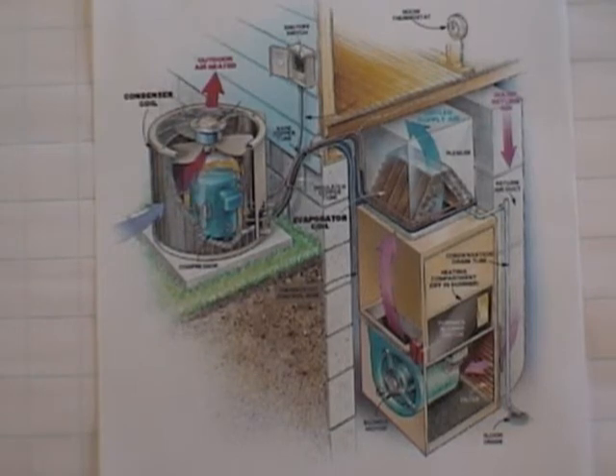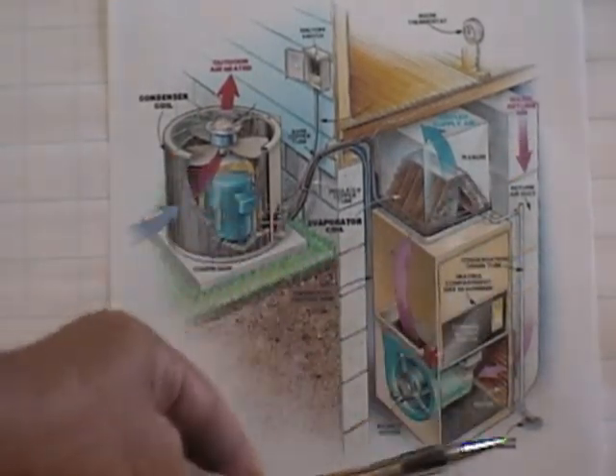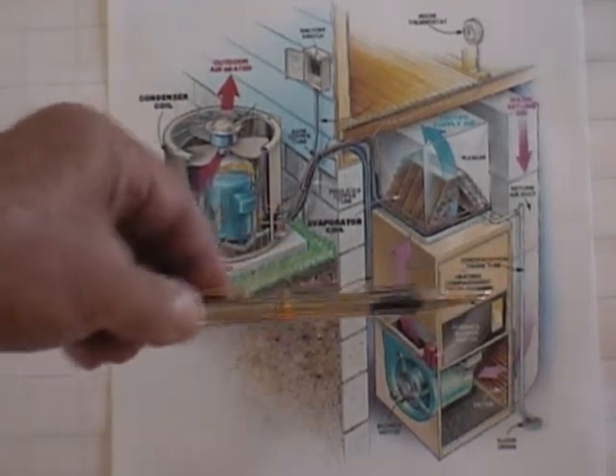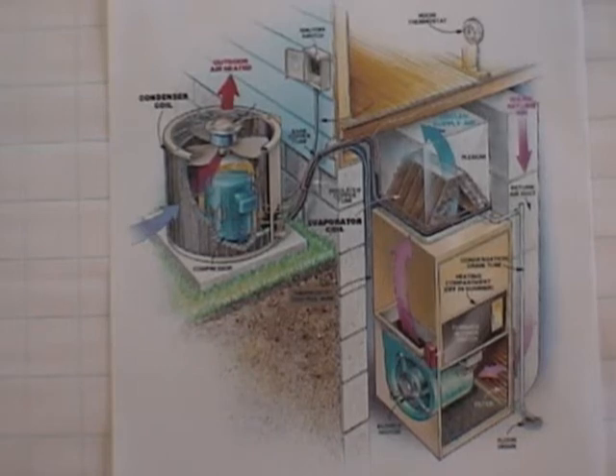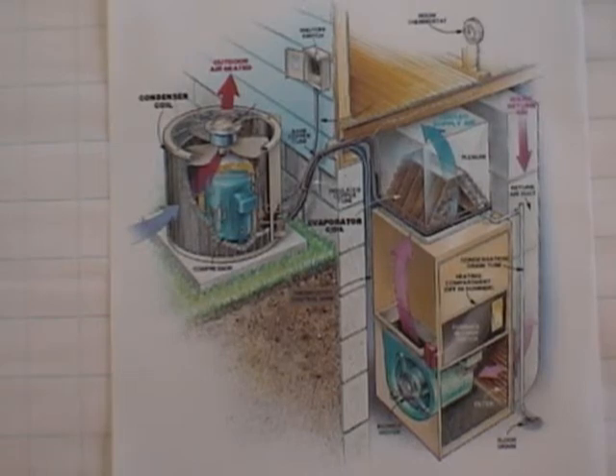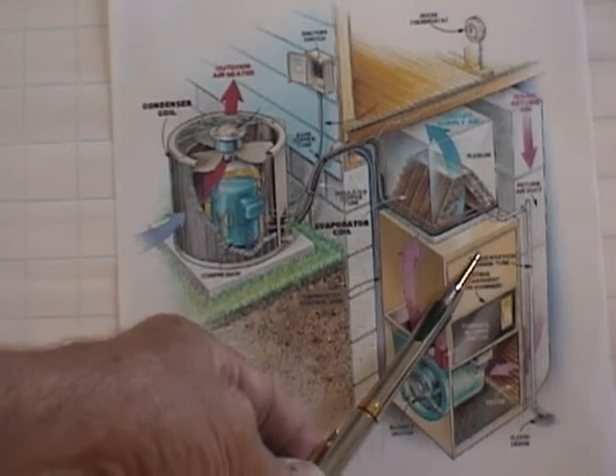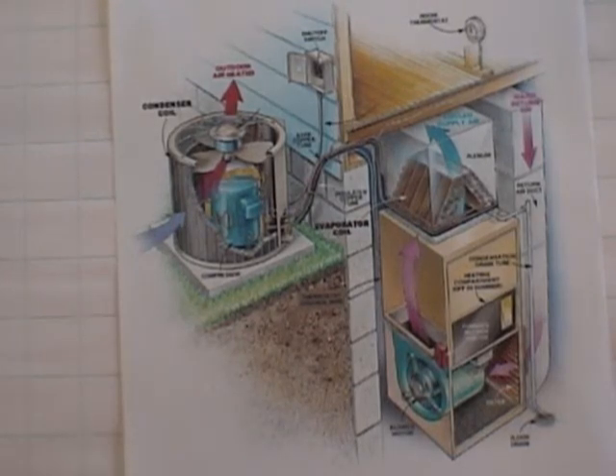Taking the wet bulb and dry bulb on the inlet side of the evaporator coil should preferably be close to the mixed air stream, so you could take it in the return air duct or in the fan suction section. However, you may get some leakage from the unit itself, especially if the furnace or air handler is located in unconditioned space — you'll get raw air with a lot of latent and sensible heat that could throw your measurements off. If there is an outside air duct into the return, you'll get a bad reading there too, so the ideal location is at the inlet as close to the coil as you can get without picking up interference off the coil.